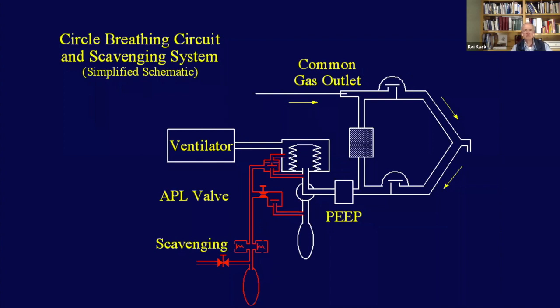So all the safety features of these anesthesia machines are geared towards somebody sitting there. It starts with most anesthesia machines not having a security lockout, so anybody who walks into the room can change things accidentally. Many ventilators have that lockout so that you have to have a password or something to change things. Another concern, of course, is that the alarm systems are made, as far as the loudness goes, for somebody sitting right next to it. Different story in the ICU, where alarm systems often are coupled to central stations, or they're loud enough for people to hear them.